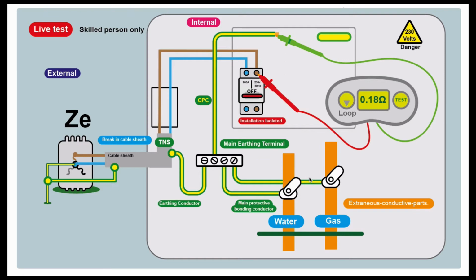The reason why parallel paths can be a problem is because they give us a false earth. If there was a break in this metal cable sheath, we might not actually have an earth path, so the installation wouldn't be earthed. But we get the impression that we have an earth path because we're reading the earth through the gas and water pipes. And there's the potential further down the line that the gas and water might be swapped out for plastic pipework, then you wouldn't have any earth at all. You're not supposed to use gas or water pipes for earthing anyway. You have to use an earthing conductor, either a TT, a TN-S or a TN-C-S earthing conductor to earth the property. So yeah, it's important that when you do this test, you are connecting to the earthing conductor and you haven't got any parallel paths.